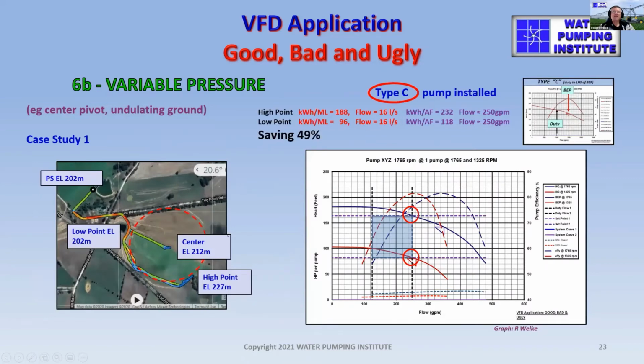So this is taken from a case study I did, and so if we start off with a type C pump where the duty is far to the left of the best efficiency point, so in the first instance, we're going down the curve. Remember, we're stuck with the same flow rate. In this case, it's 250 gallons a minute. So the efficiency at full load is on this blue curve, so it's 76%, and the efficiency at the reduced load, well, hey, look at that, it's actually higher. So as the speed of the pump came down, the actual efficiency of the pump went up. So it works in our advantage to have a pump of type C, and the savings in this case, 49% of the highest point compared with the lowest point.